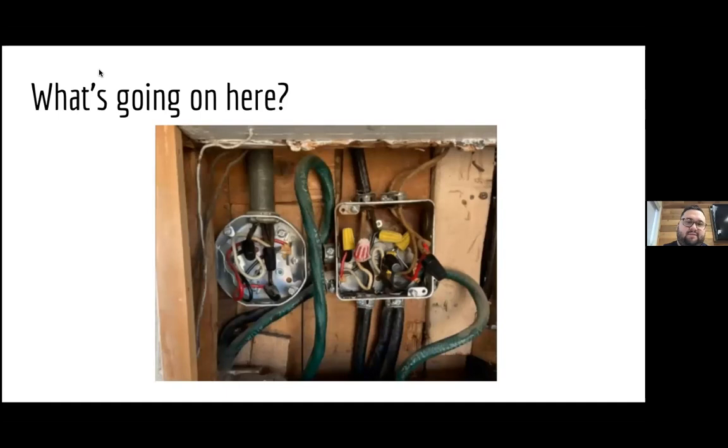And how about this one? Looks like snakes. Like a really terrible puzzle. What is that pipe on the left hand side? The pipe. The pipe. Yeah, that's, that's pretty normal. That's just, that's just the electrical coming in. That's probably looks like knob and tube in a way, but big fixed up. No. Yeah. Michelle's actually really on the right track. So this is knob and tube again. So this was actually that same house that had the open in the attic. However, this is worse. So what they did was instead of fully fixing the knob and tube, somebody just replaced the connection points with aluminum wiring, which is also not okay. So this is kind of like a double whammy of bad. So this had aluminum wiring as well as knob and tube in the same house. So that's a first for me. Wow. So they were on borrowed time. In other words. Yeah, potentially. Right.